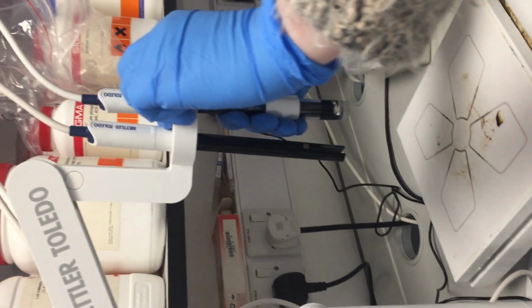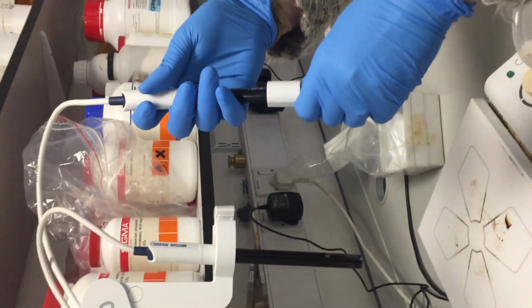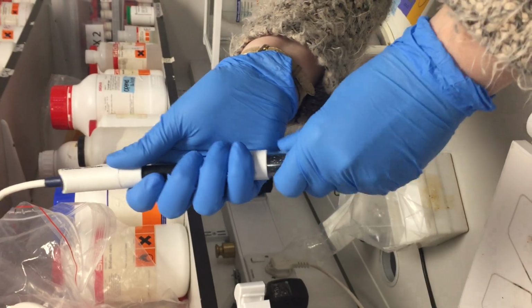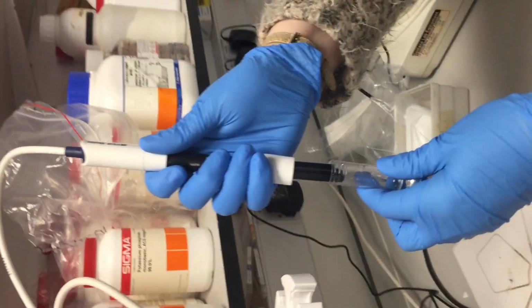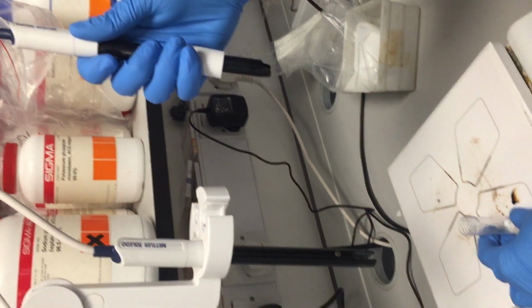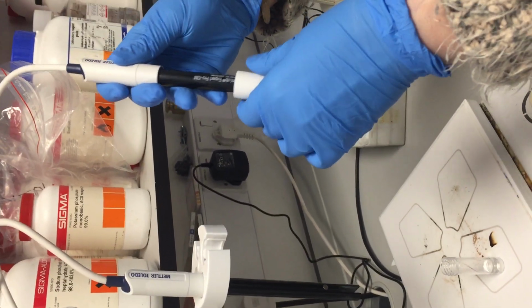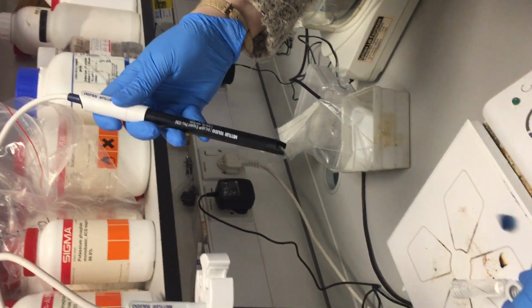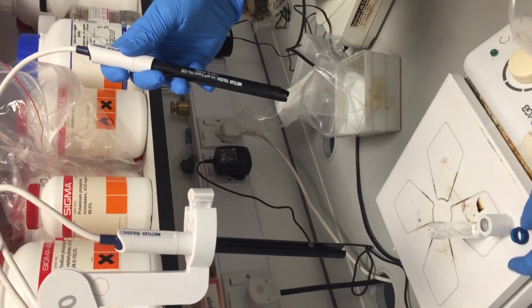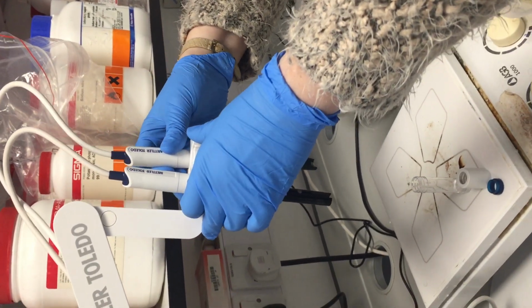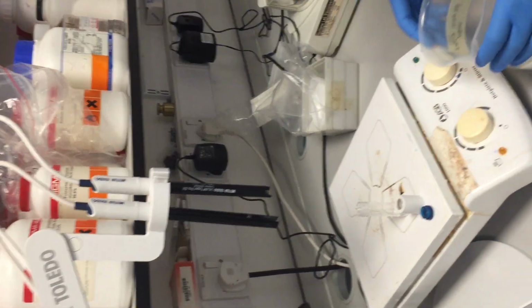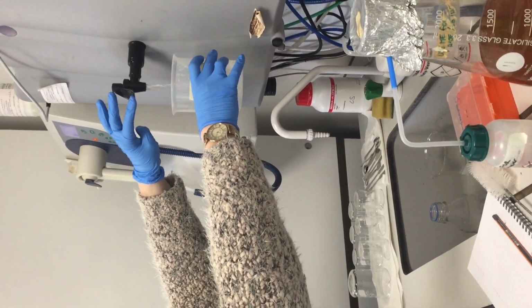So to put the pH electrode inside, you must unscrew it like this, and be very, very careful with the pH electrode because we don't wish to lose it. So you can remove this part. Then this will be our electrode for use. So let's take the water. And we have water for pH measurements to clean out the electrode.